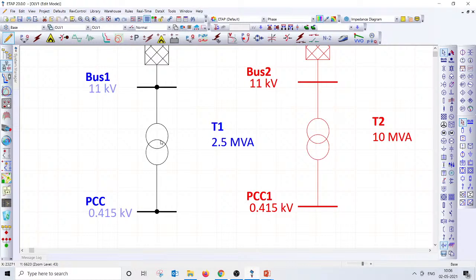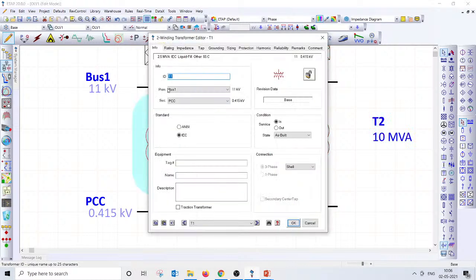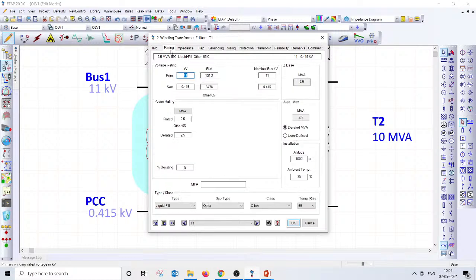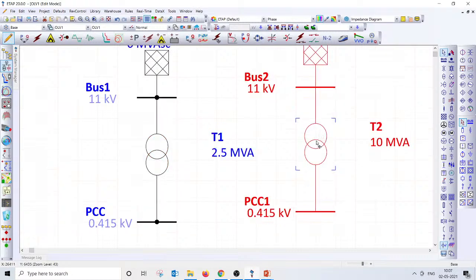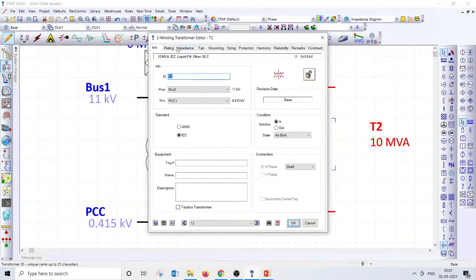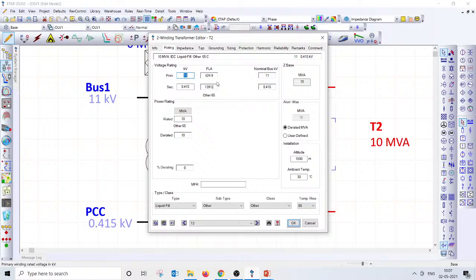Right. So let me highlight some area so that you can understand why we cannot go for a 10 MVA transformer. If you take a 2.5 MVA transformer, on the 11 kV side the full load current is 131 amps, and on the LV side, that is the 415 volt side, the current is 3478 amps. 3478 amps is the full load current. And if it is a 10 MVA transformer, then it will be just 4 times. That's well known. The full load current on the 11 kV side is 524 amps.